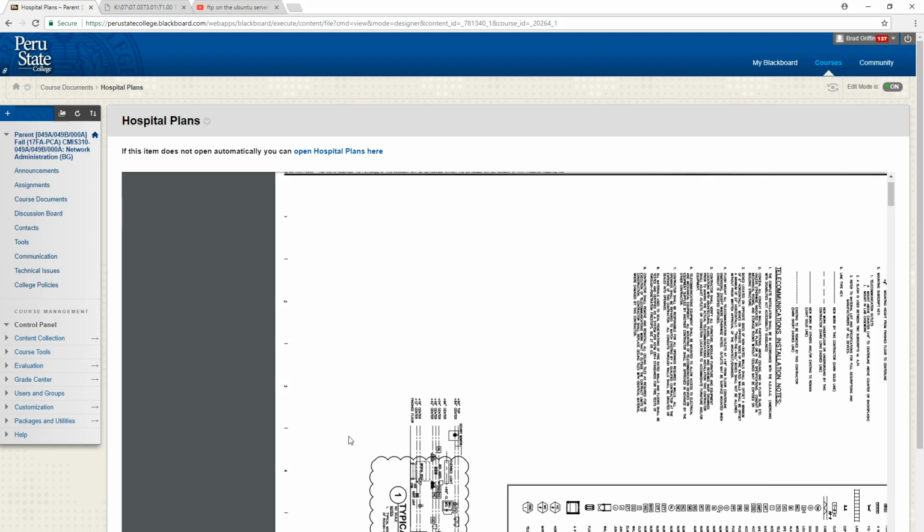Well, there's a hallway in this building that we were originally going to be able to run cables across. And the architect decided, you know what, we need to make that what's called a clerestory. So they opened it all the way to the roof with windows in it, essentially making this great lighted feature. Well, guess what? It made the data runs well past 300 feet, so we had to change some of the plans on the fly and get a contractor to do a change order for it. That was kind of an exciting thing to do.